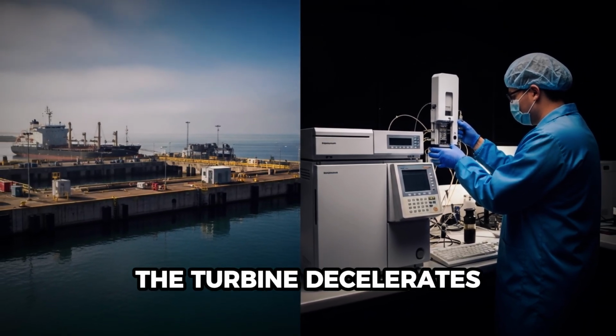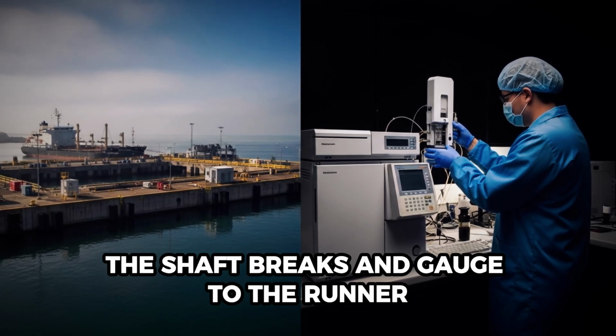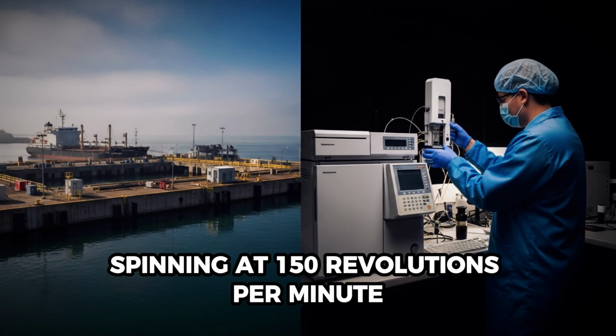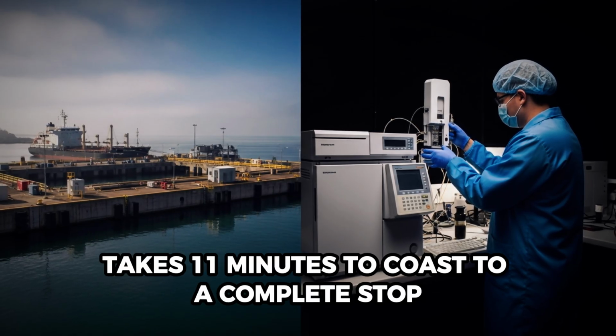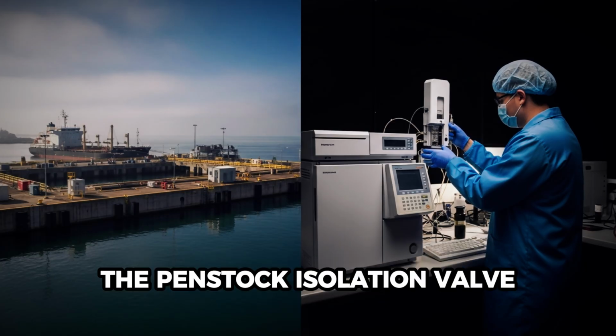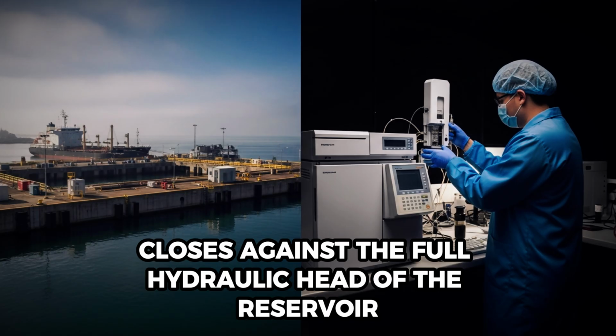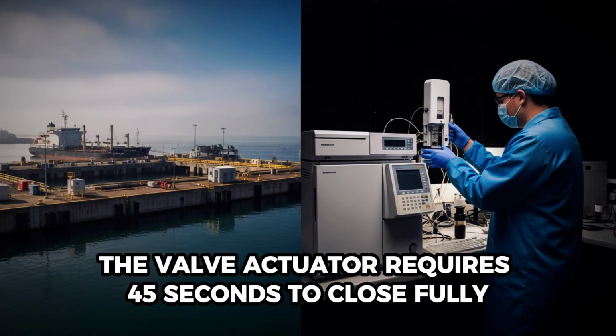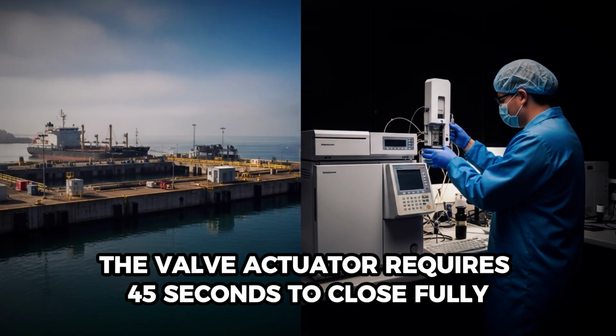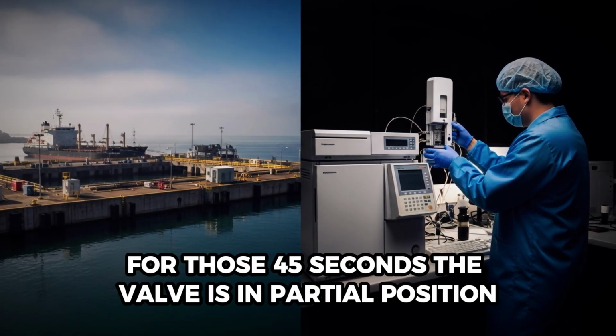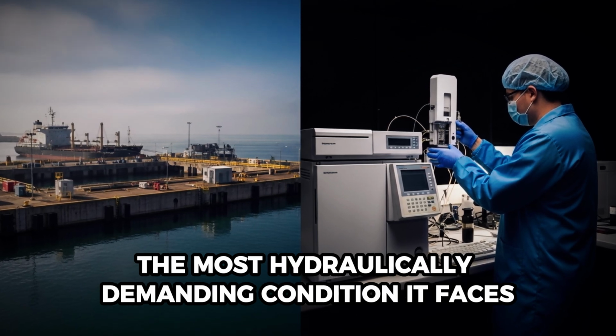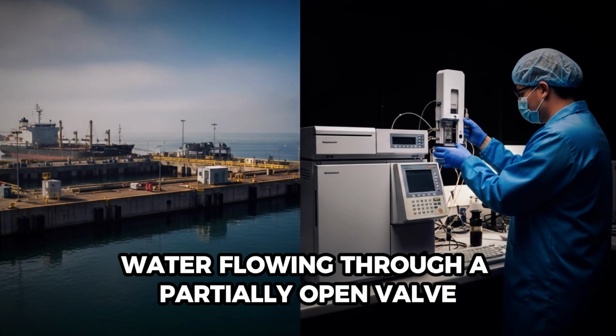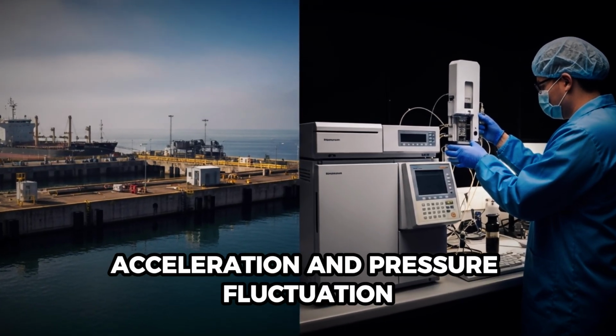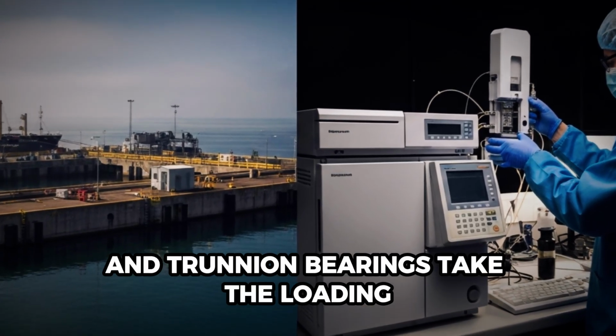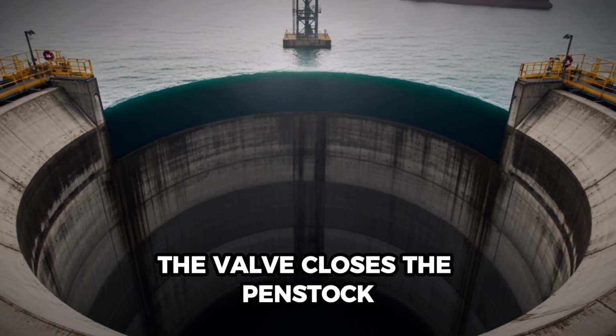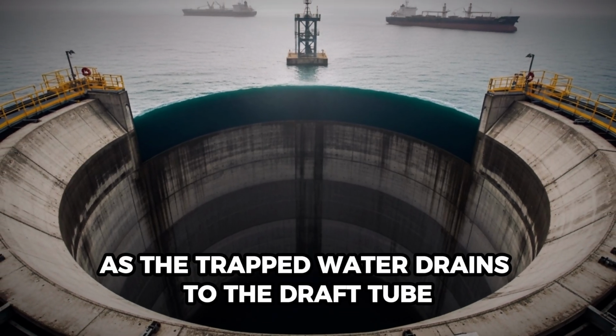The turbine decelerates. The shaft brakes engage. The runner, 300 tons of steel spinning at 150 revolutions per minute, takes 11 minutes to coast to a complete stop. The penstock isolation valve, 7 meters in diameter, closes against the full hydraulic head of the reservoir above. The valve actuator requires 45 seconds to close fully. For those 45 seconds, the valve is in partial position, the most hydraulically demanding condition it faces. Water flowing through a partially open valve experiences velocity acceleration and pressure fluctuation. The valve's seating faces and trunnion bearings take the loading. The valve closes. The penstock pressure drops to zero as the trapped water drains to the draft tube.